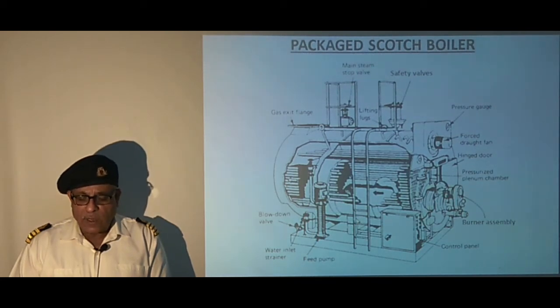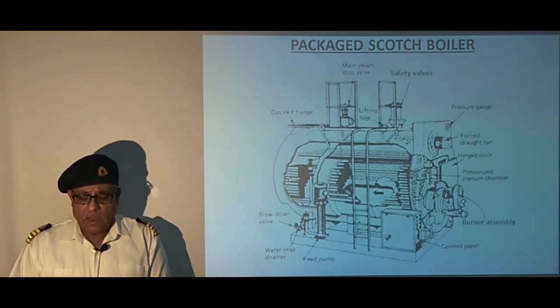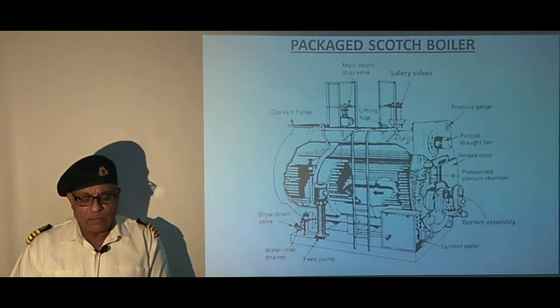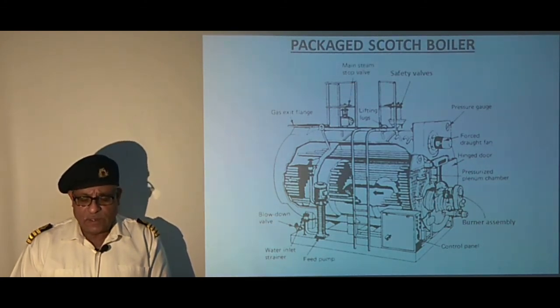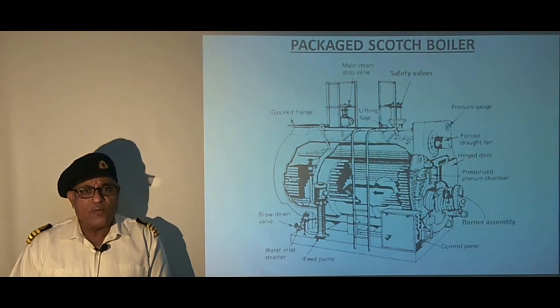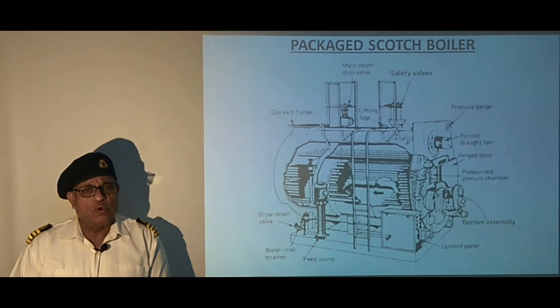This boiler was heavily constructed and had a durable design. For ease of inspection and maintenance, front and rear smoke box doors were davited. It required very low maintenance. The boiler was usually operated at 10.5 bar with an efficiency of 81 percent, although it had a maximum working pressure of up to 20 bar.